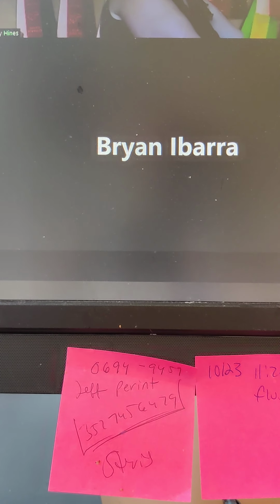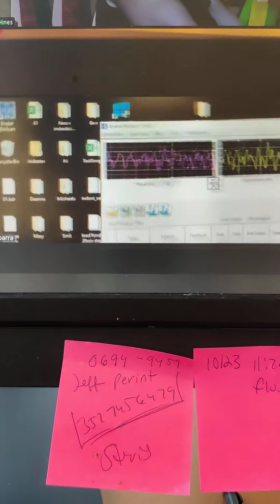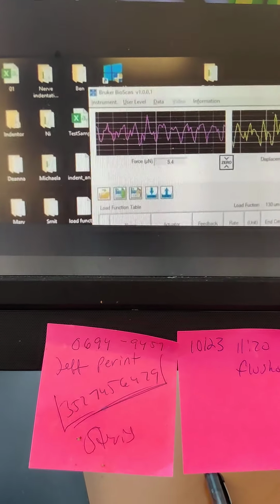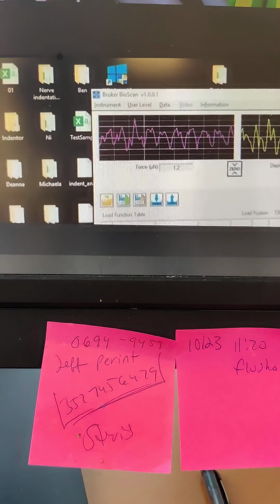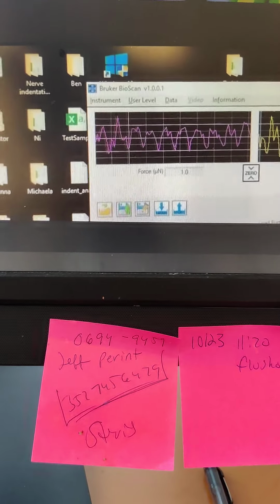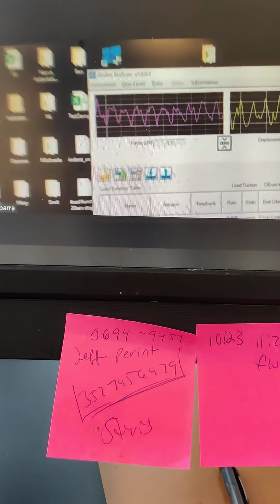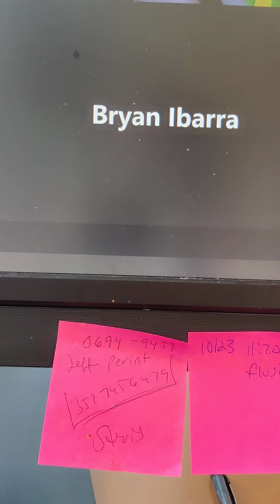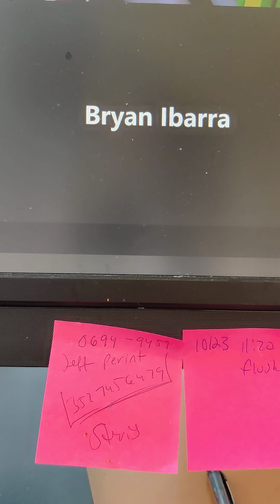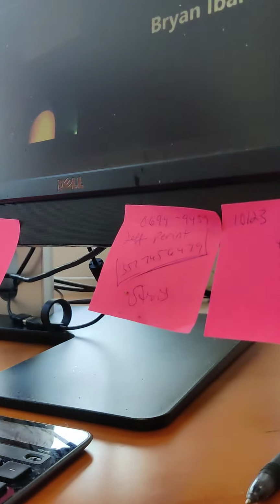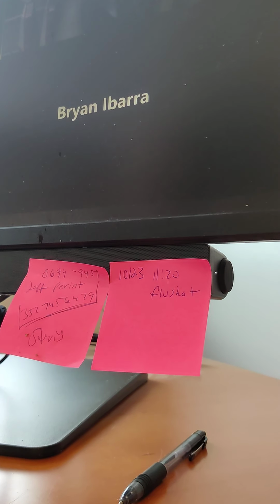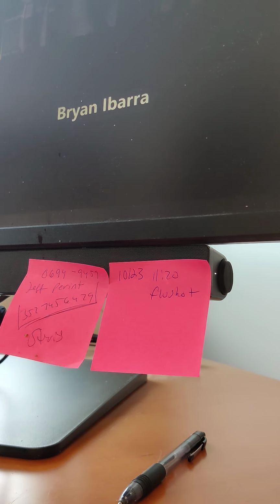Book extra time. So make sure that the noise, there's a thing to talk about here. So the noise, now that it's calibrated, the force should remain between positive and negative 10 for the most part. Micronewtons. Okay. So it looks pretty good there. That's what the calibration did to minimize that noise. This says you may need to repeat calibrating the sensor 2 to 3 more times if it's still too large, because the table might have moved or something electrical might have happened randomly to cause it not to calibrate correctly.